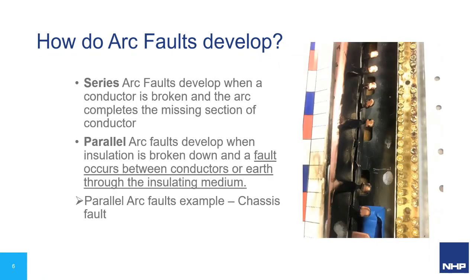So there are two different types of arc faults that can develop. The one that we're seeing here is what's called a parallel arc fault example. That's where you've got two different conductors and it actually jumps across between the two. And that second conductor can be neutral or earth as well.